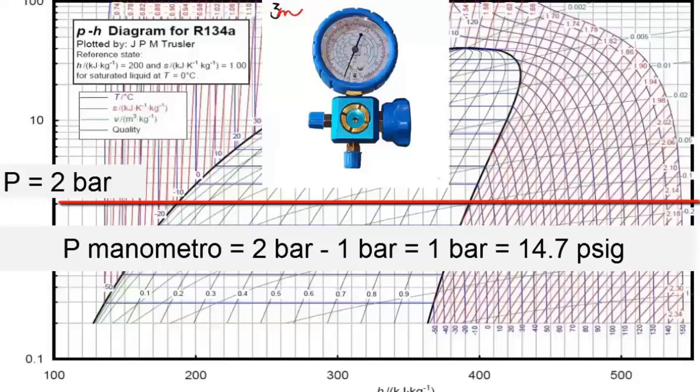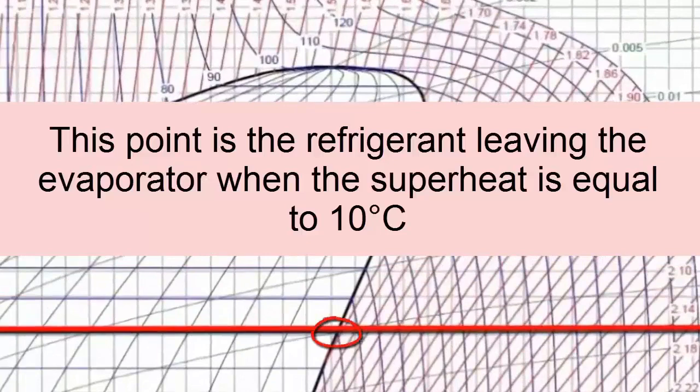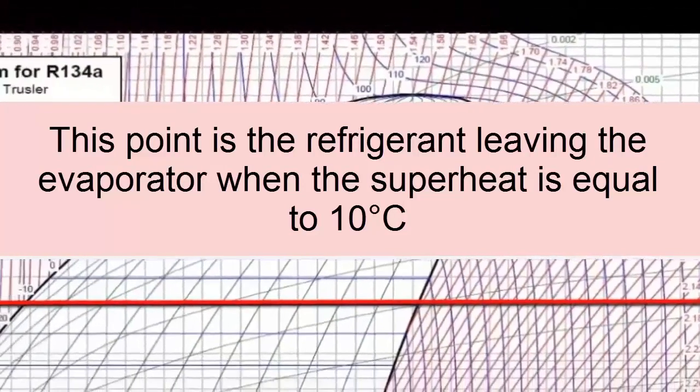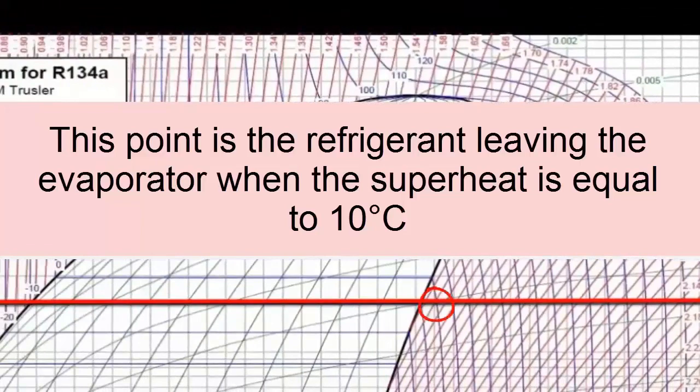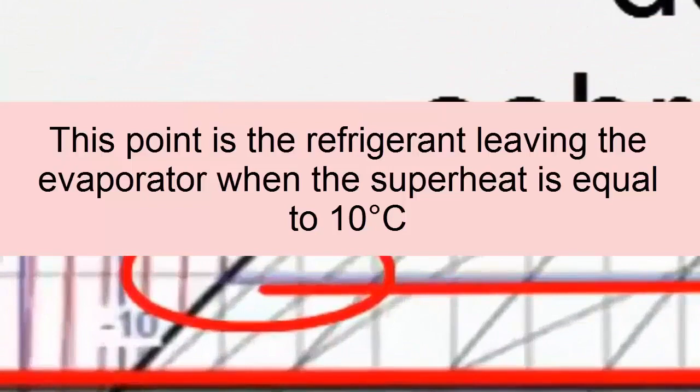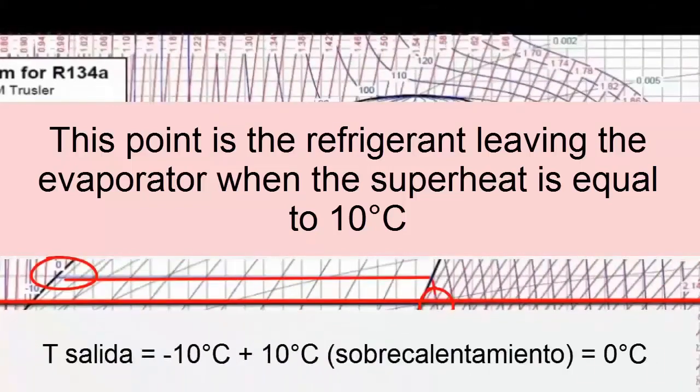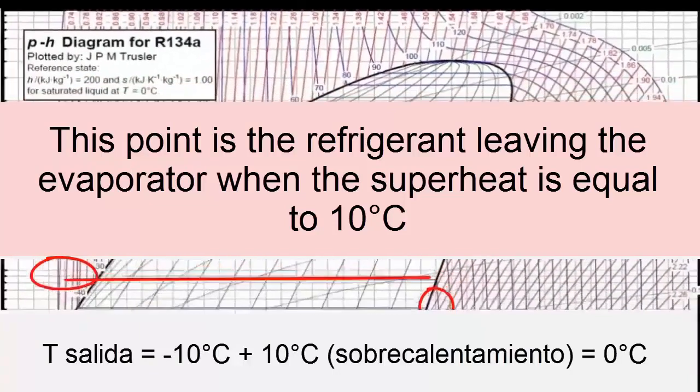The low or blue pressure gauge should read 1 bar or 14.7 psi. This point represents the outlet of the evaporator when there is no overheating of the refrigerant. But when there is an overheat of for example 10 degrees, then the evaporator outlet point moves to the right, because by adding the minus 10 degrees of the evaporator plus the 10 degrees of superheat, a temperature of 0 degrees is reached. Remember that superheating is the increase in temperature of the refrigerant in the evaporator.